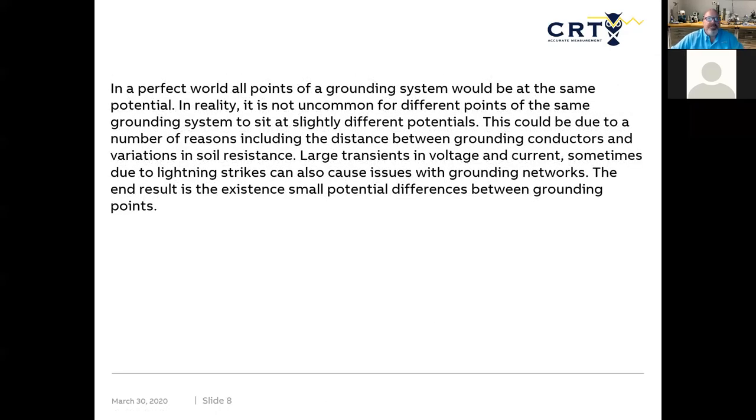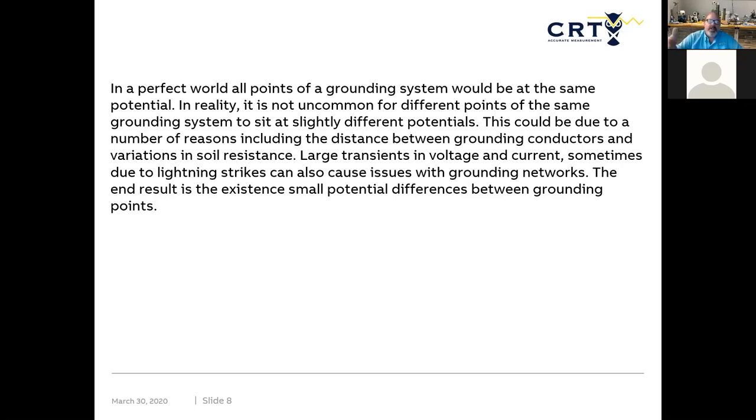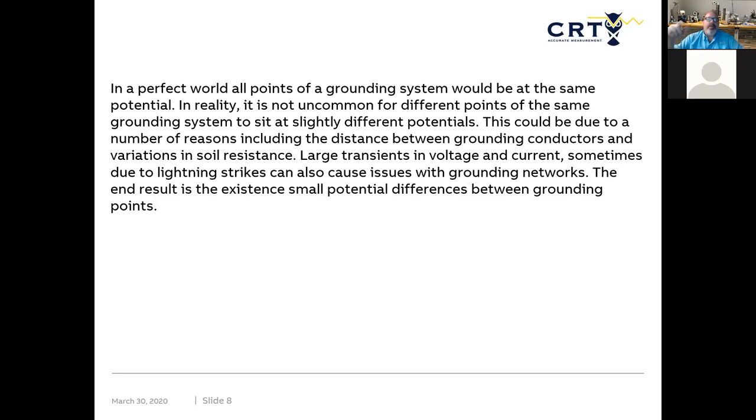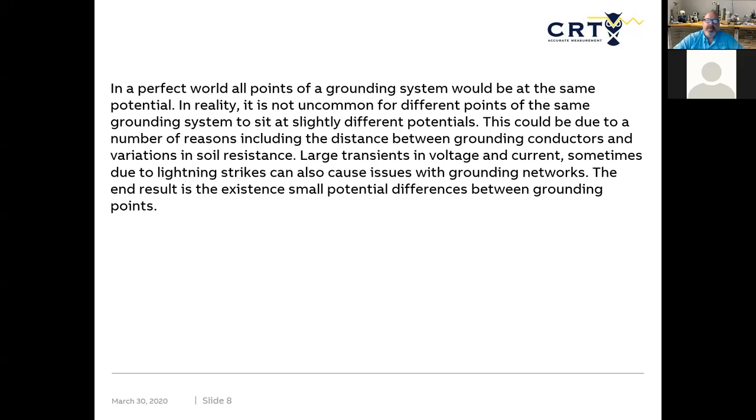In the perfect world, all points of a grounding system will be at the same potential, but in reality it's not uncommon for different points of the same grounding system to sit at slightly different potentials. So if I'm grounding at different points across along my circuit, I can have difference of potential across those and it will change the analog potential that I have and throw off my readings.